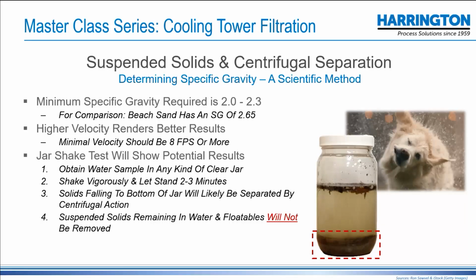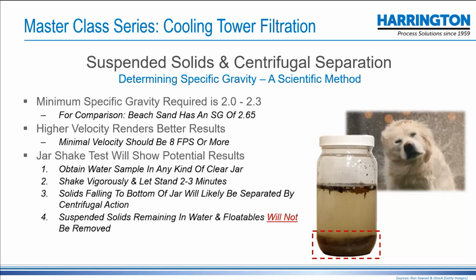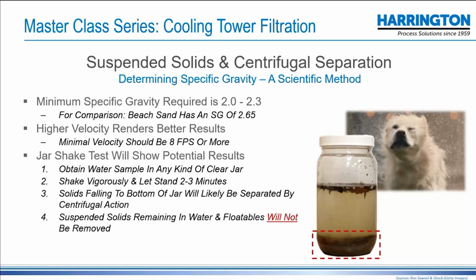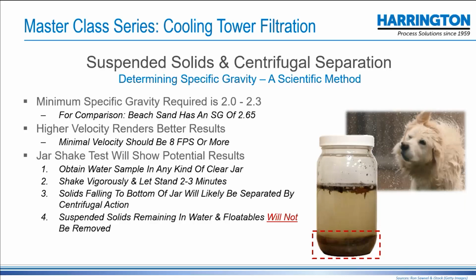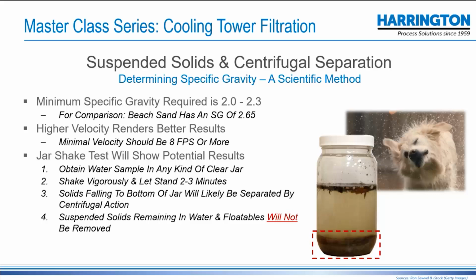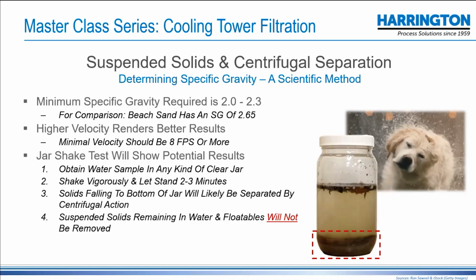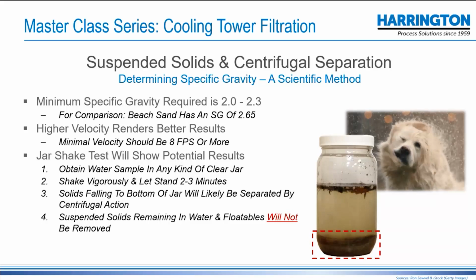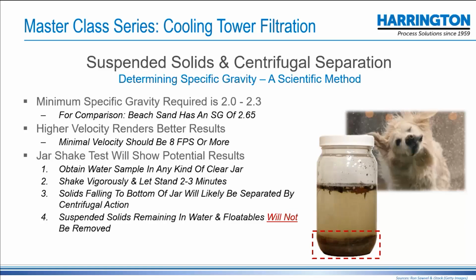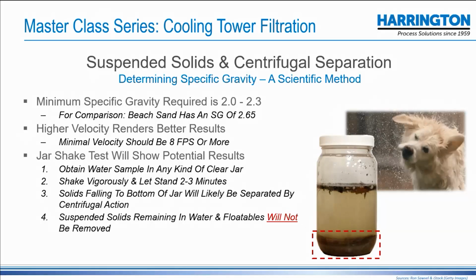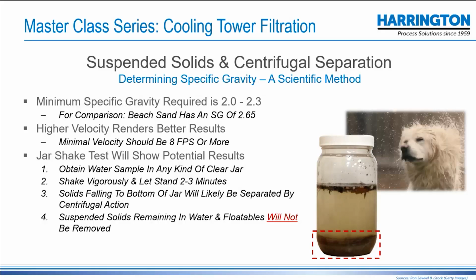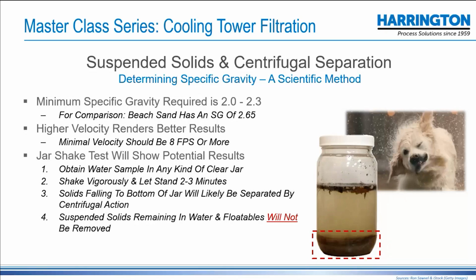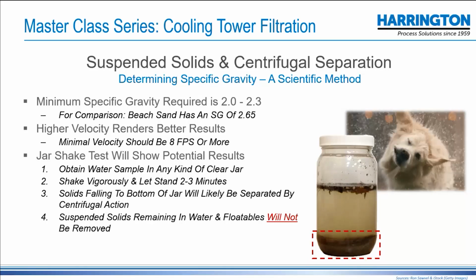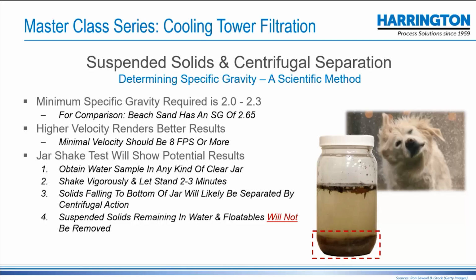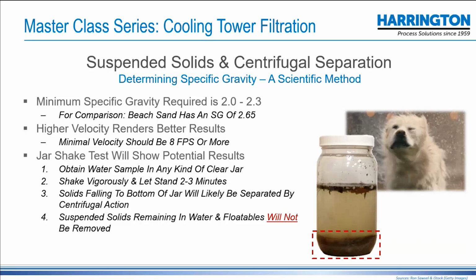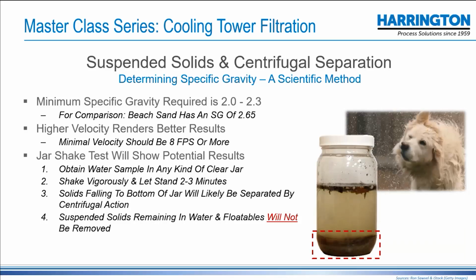You take a jar of your water, you shake it vigorously for about 15, 20 seconds, set it down, let it rest for 2 minutes, and what settles at the bottom is what the centrifugal separator is going to get out. What's above the sludge layer that you see form at the bottom within 2 minutes is going to go right through it. And so you can test. I mean, if you do want to try a centrifugal separator, you do want to try this test. All you need is a mason jar, not real technical.